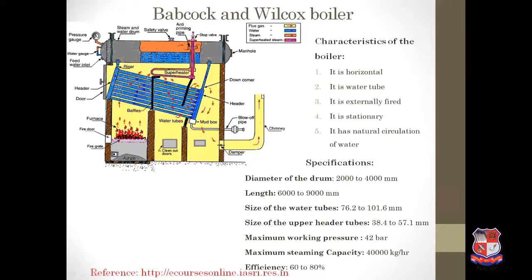Inside the Babcock-Wilcox boiler, baffles are provided so that hot gases move in a sine wave form during their movement, covering the maximum surface area of the water tubes. After finishing this sine wave movement, the hot gases leave the boiler. Important mountings include a pressure gauge to read the steam pressure inside the boiler and a water level indicator to monitor the water level.